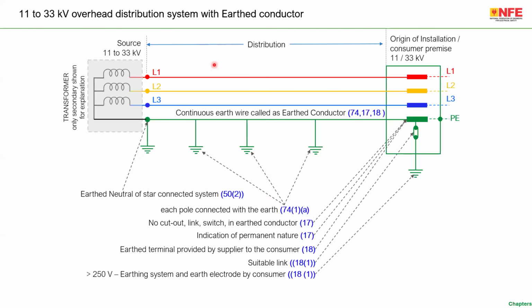Like this, multiple regulations set several requirements. Here, what I am saying is, for example, the secondary side of a source which is feeding 11 kV to 33 kV power to a transformer. Example, in a consumer premise, this also can be a transformer on the roadside which is feeding low voltage supply to multiple houses. So basically, if we look at the regulation, there must be a continuous earth wire. In case of an armored cable, there is no shield wire, there is armoring for the metallic fault return path. Now, in this particular case, how can you calculate the short circuit current?